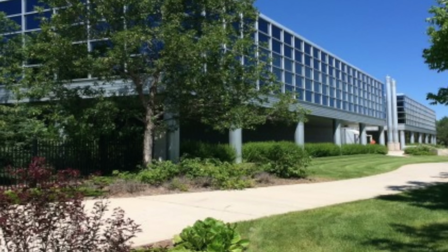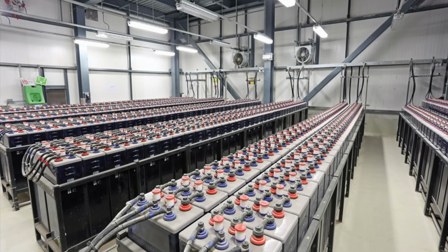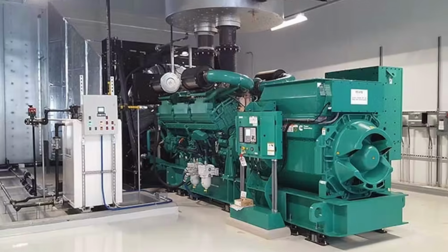Back when I was in college, my father-in-law ran the IBM data center in my hometown, and he was responsible for all the facilities, including the UPS for the entire office building. Like a consumer online UPS, it was set to continually convert the incoming AC, whether from the utility or generators, into DC to keep the batteries full. Those batteries were made up of huge banks of 2-volt lead-acid float batteries that completely filled a very large room. The battery power was then always continually converted back to sine wave AC, and in that way, if the power ever went out, everything would be running off the batteries as if nothing ever happened until the big diesels kicked in. Those generators then simply took the place of the utility power, charging the batteries back up as needed and powering the AC to DC to AC conversion process.